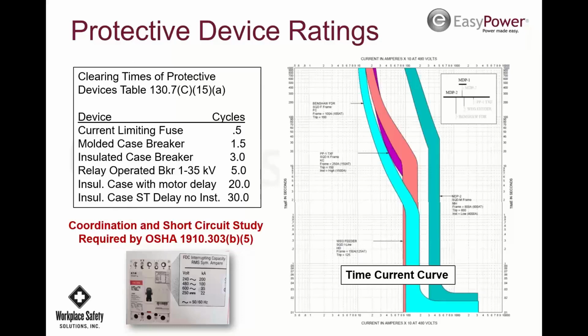To do the arc flash analysis, you've got to collect the same data that you would for a short circuit and a coordination study. That's why your arc flash study will tell you if your coordination is good, if your short circuit is good, and if everything is rated for the short circuit fault current. It's important to read that portion of the study as well, to make sure that you understand. So look at the recommendations from the engineer that does the study. This is an important part of it.